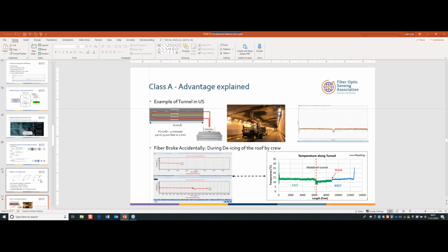Getting back to the question about how easy it is to replace, it's very simple. If a cable is broken, you remove a few meters or inches or feet of that area, and then you can bring in a new cable and do a fiber optic splice. This fiber optic splice is very simple. The connectivity is also quite simple in the sense that when you do this splice, it's not a new zone. It's the same zone as you had before, and the system is still continuous.